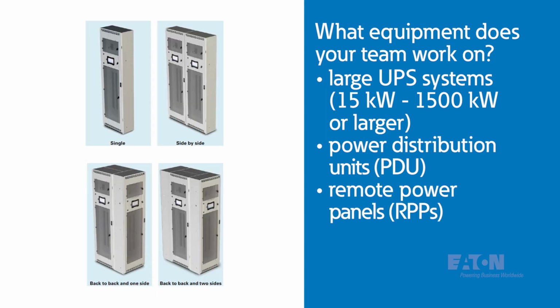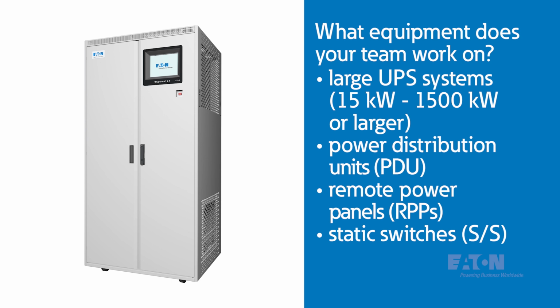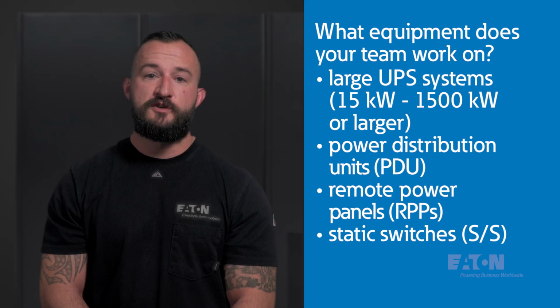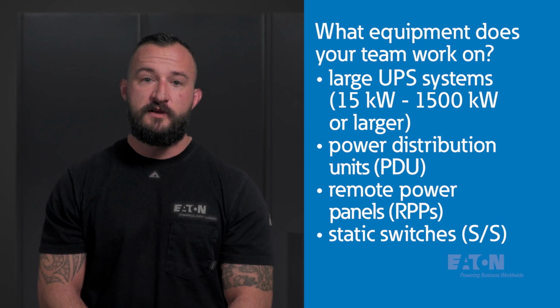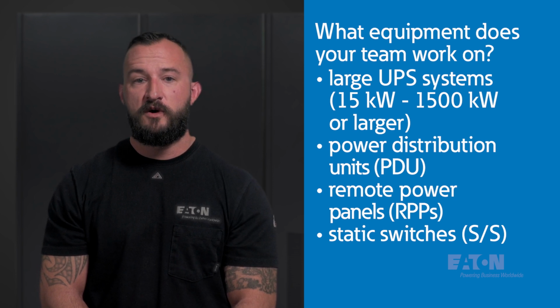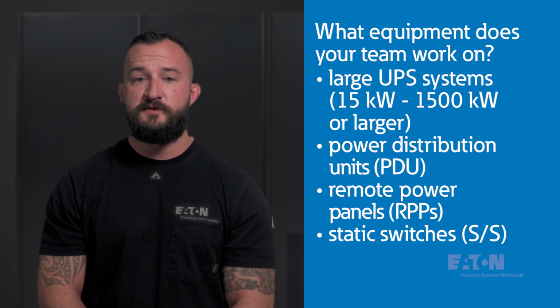We also work on remote power panels, or RPPs, which are similar to PDUs but don't include transformers. They have one or more panels in the enclosure that typically feeds EPDUs or servers directly. And finally, we also work on static switches, which allow fast transfer from one source to another, usually sub-cycle transfers before the servers are even affected. Our job is to ensure that we are well-trained and understand how each piece of equipment works and how to fix it or field modify it if necessary, to help customers with issues.